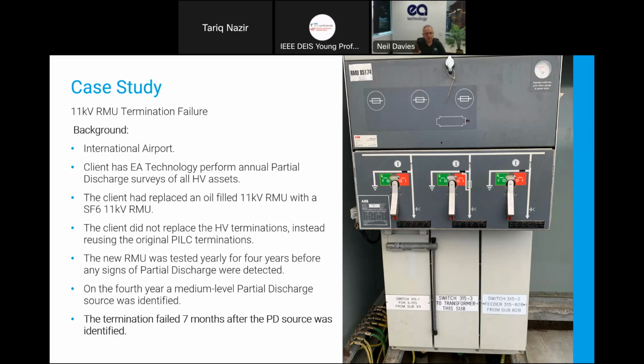What they'd done at the time, though, is not replace the HV termination. So instead, they reused the original PILC terminations, paper insulated lead covered cables, those original terminations, and put a new ring main unit on top. Now, the new ring main unit was tested annually for a 4-year period, and then partial discharge was detected. On the 4th year, a medium level source of PD was detected. Unfortunately, before they intervened, the termination failed some 7 months after the PD source was identified.